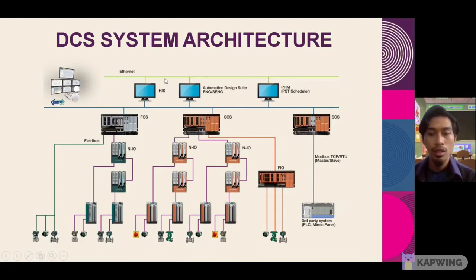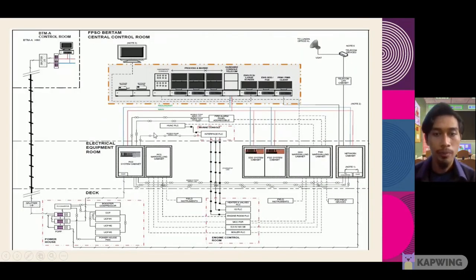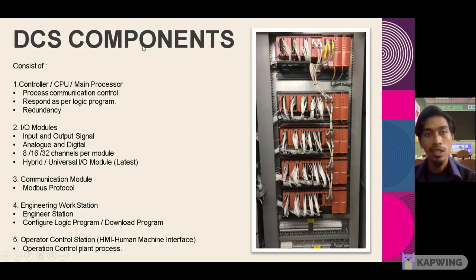So this is a figure for the DCS system architecture from the Ethernet to the output. This is a single line diagram for the central control room. It's for the DCS components, which consist of: number one, controller or CPU or main processor. Its function is to process communication control, respond as per logic program, and redundancy. Number two is the I/O module for the input and output signal. Number three is the communication module for the Modbus protocol. Number four is the engineering workstation for the engineer station. And last is the operator control station, HMI, to operate and control the plant process.